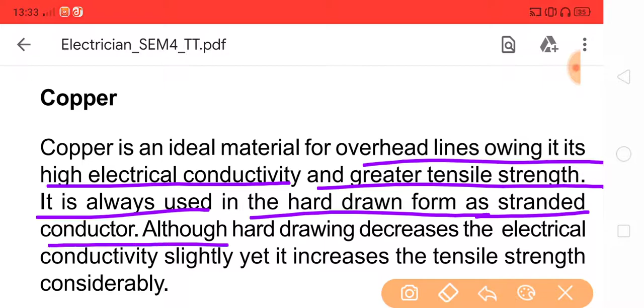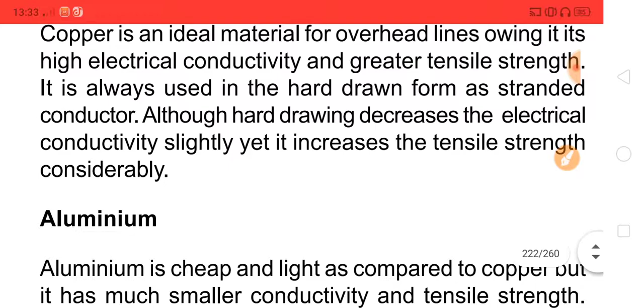Copper. Copper is an ideal material for overhead lines owing to its high electrical conductivity and greater tensile strength. It is always used in hard drawn form as a stranded conductor. Although hard drawing decreases the electrical conductivity slightly, it increases the tensile strength considerably.